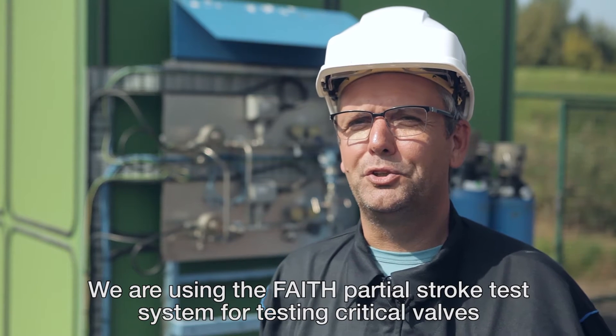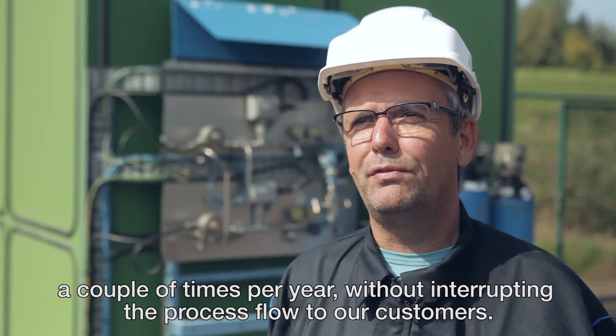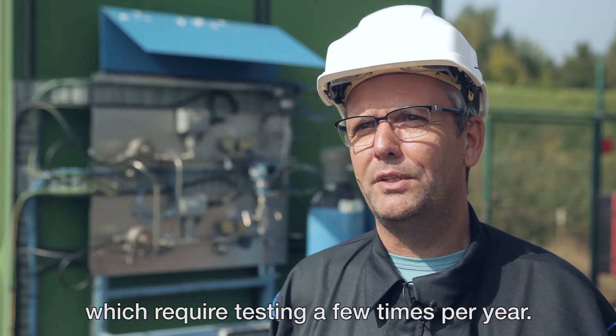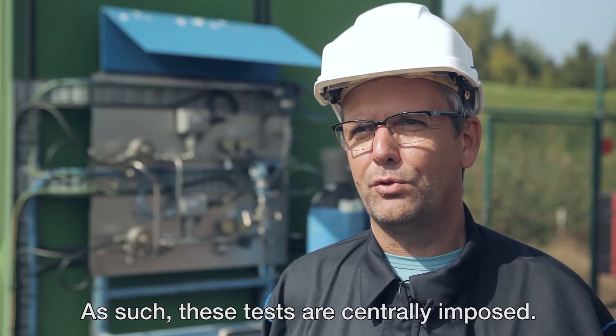We use the partial stroke system to test the valves a few times per year without breaking the flow to the client. The tests are implemented by the maintenance procedure. These ESD valves need to be tested a few times a year. ESD is an important element for safety, used across the group.